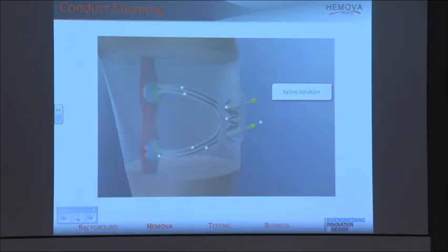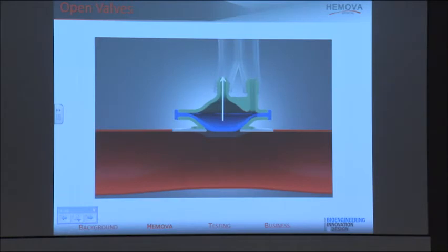After the dialysis session, the valves are closed and the system can be cleaned out with a solution as seen in this picture. Now let's take a closer look at the valve design. Our valve is activated through pressure. So by pulling saline through the center port, as shown before, which results in pulling saline through this tube right here, the valve can be flipped up, allowing blood to flow into our device and undergo dialysis.